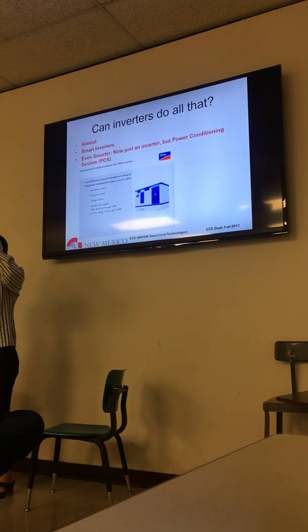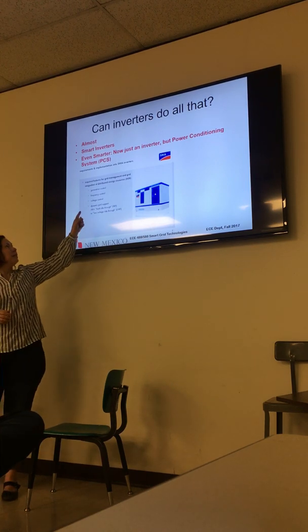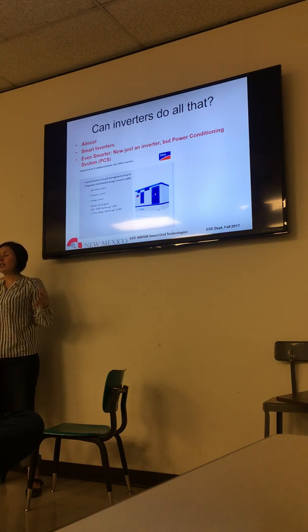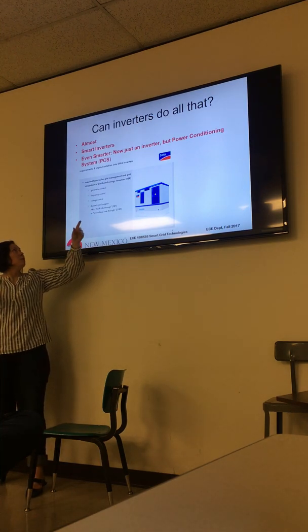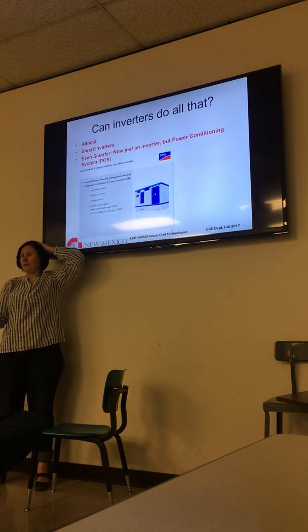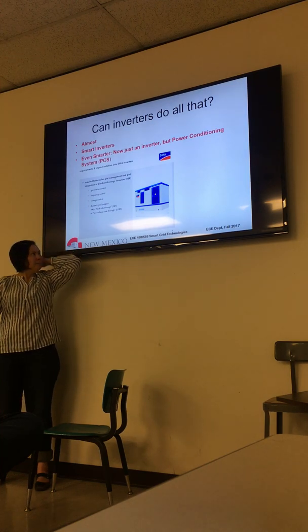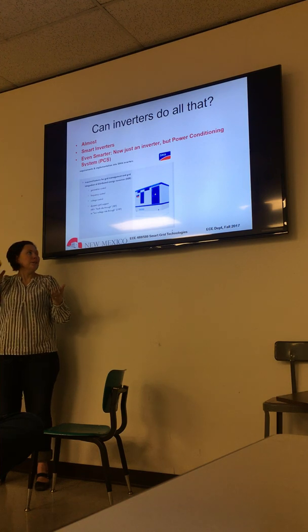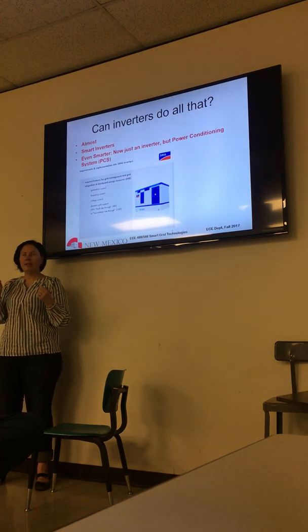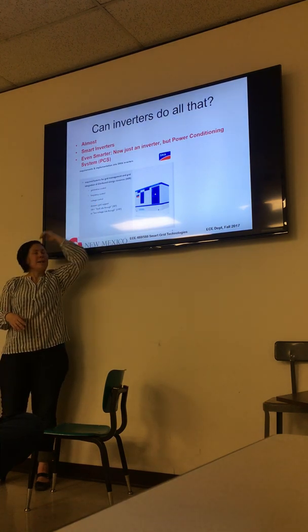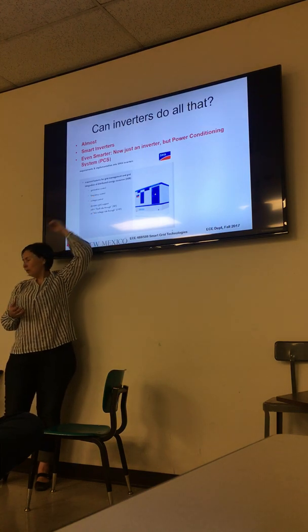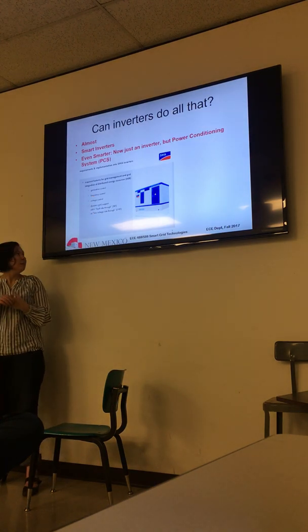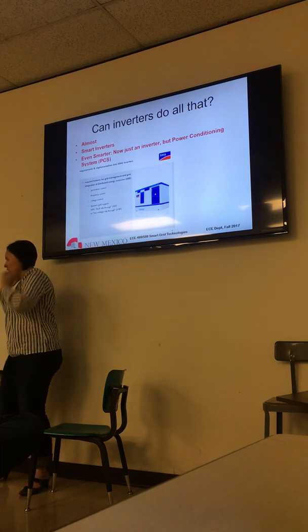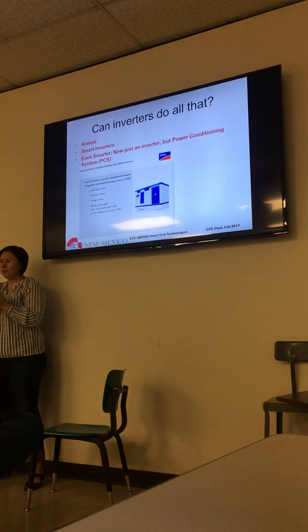So what you discussed is taking DC, converting it to AC, pretty good quality sine wave, so that you have low THD, right? But now we have all of these requirements from inverters, and some of them are not microinverters but large-scale, megawatt scale inverters that can do other things like voltage control. Sounds intuitive, right? Because you clamp the voltage on the output stage, so that will be AC RMS clamped operation. So voltage control sounds okay, something you would already expect. But then there are things like frequency control, inertia, dynamic grid support, fault ride-throughs - those are all the interesting things you get now from smart inverters.